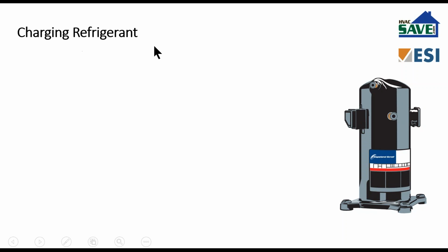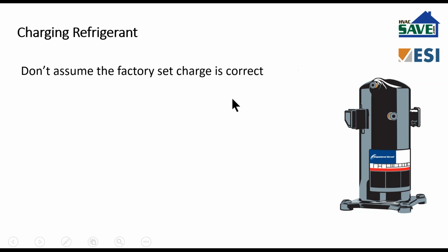Okay, now charging refrigerant. Please do not assume the factory set charge is correct. That's based upon a certain line set, which is rarely the case, or oftentimes not the case, okay?